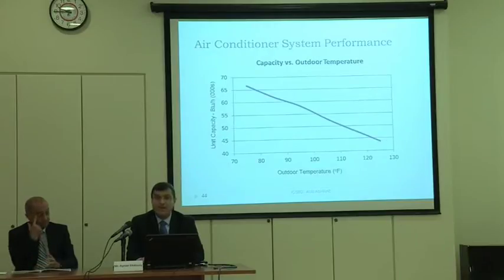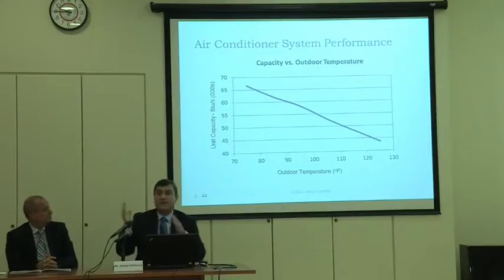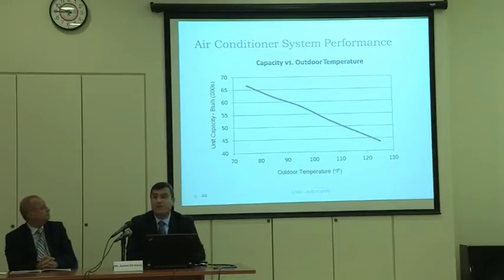The machine behaves differently at high ambient, and this is very important to see. If I bring a machine to the lab and increase the outdoor temperature from, for example, 35 to 46, you can see very clearly that the cooling capacity will go down sharply. The same machine will give you, for example, 2 tons at 35, and it may give you 1.8 or 1.7 tons at 46. So the cooling capacity goes down with the temperature, no matter what the design of the machine is. Anytime the temperature goes high, the cooling capacity will go down.